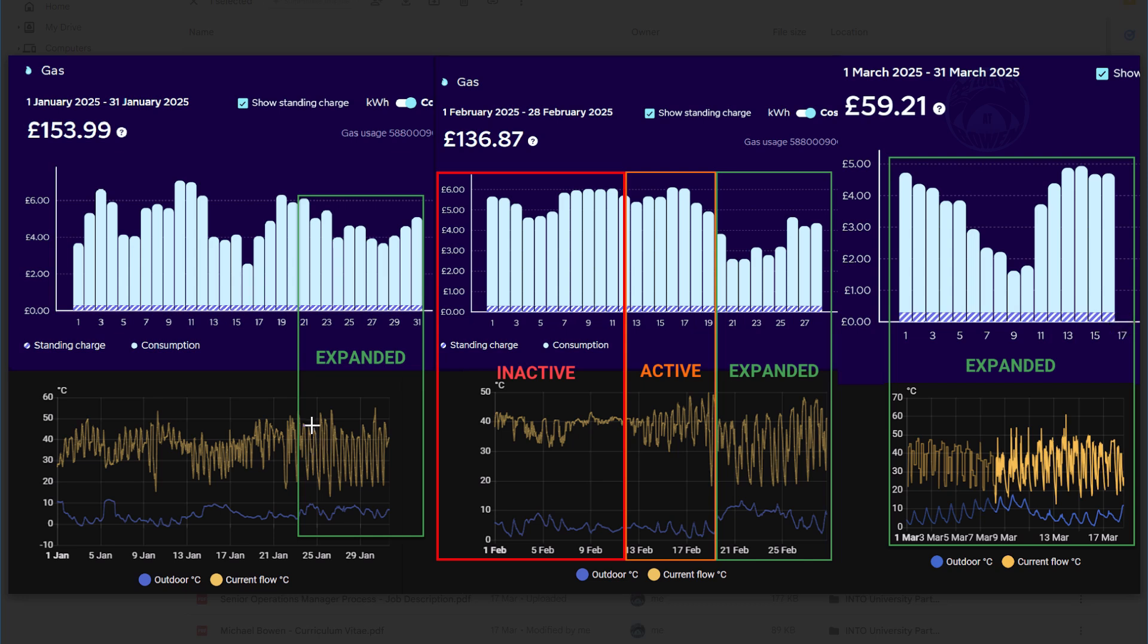Expanded has or makes use of timers. So you set your different timers and while the timer is active the boiler is on and when it's inactive it drops off, which is why you see these quite large spikes from top to bottom. When it's at the bottom that's when it's outside of the timer and when it's at the top it's either during the timer period or someone's running a hot water tap and that's why it spikes to above 50. But in general it runs just above 40 and between 30 and 40 and then anything outside is obviously outside of the timer.